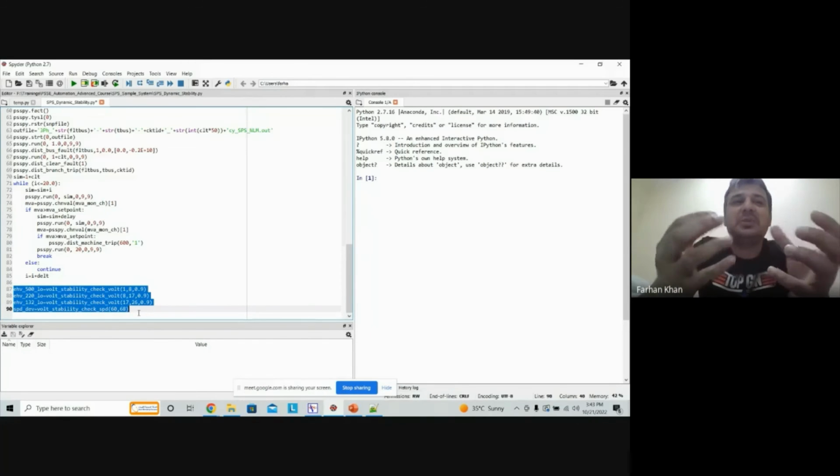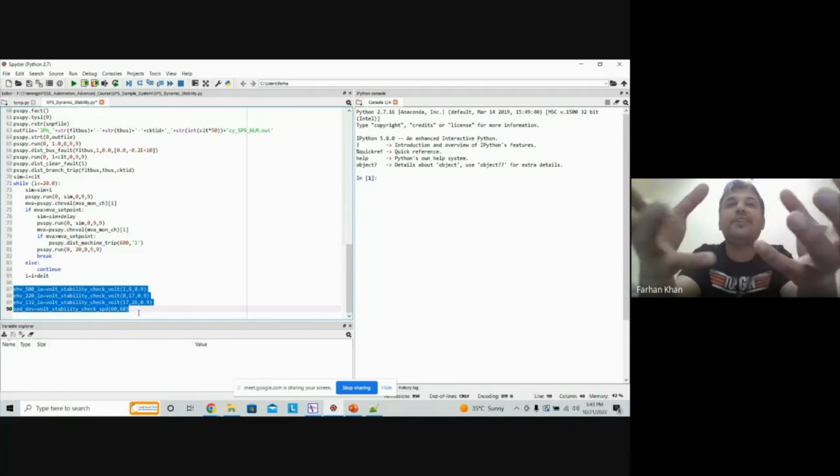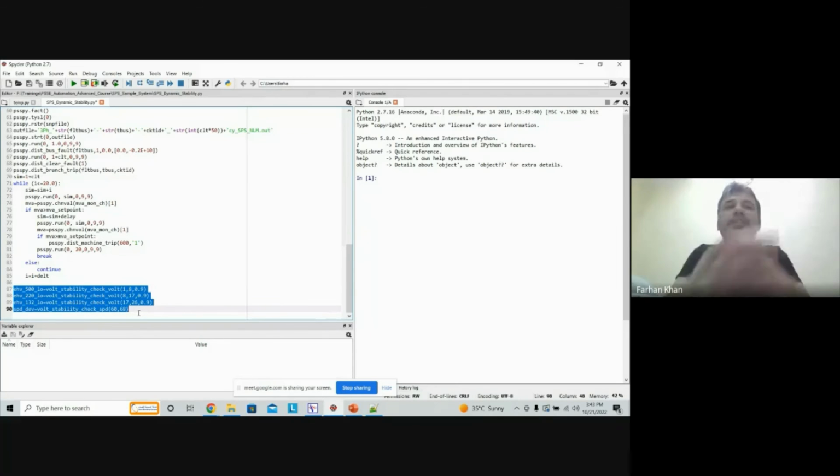So I want to make sure that once I reduce this reactive power within my system, whether my voltages within my system and these motors within my system are well within my range or not. So that is why I monitored these things.